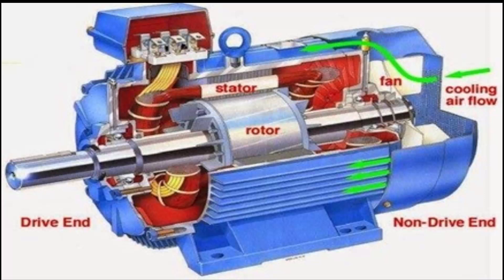When the motor is powered up with three-phase AC supply, a rotating magnetic field is produced within the stator circuit, which induces the EMF in the rotor. Because the rotor is short-circuited through the end ring, current is produced due to the induced EMF. This current interacts with the rotating magnetic field, then torque is developed in the rotor in the direction of the rotating magnetic field. This is the main basic working principle of every induction motor.